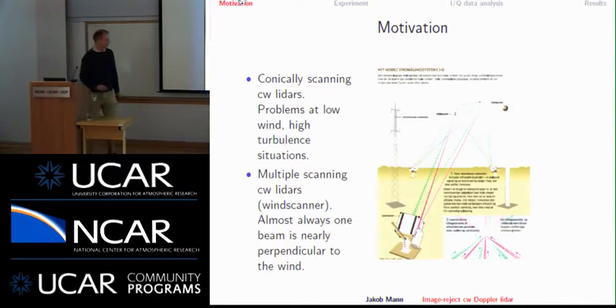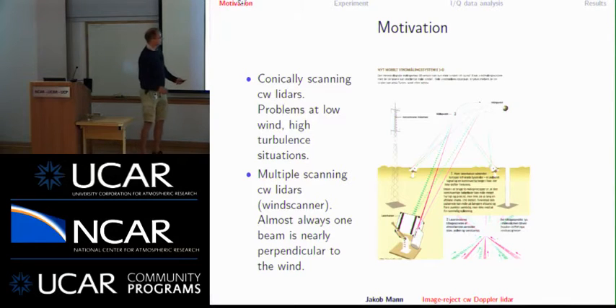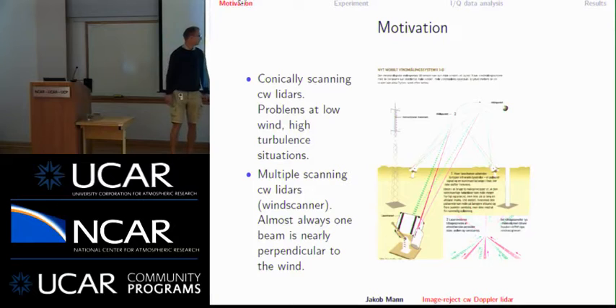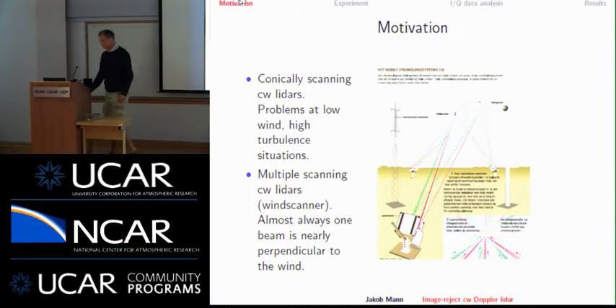Another thing is that we want to do a lot of measurements where we use 3 simultaneous lidars and scan around to map flow around the turbine or any structure. And it's almost impossible to plan the experiment, so you will never have the flow perpendicular to one of the beams. No matter what you do, one of the beams will have the flow perpendicular, so you'll have 0 velocity on one of the instruments. So not being able to measure close to 0 is a problem for us.